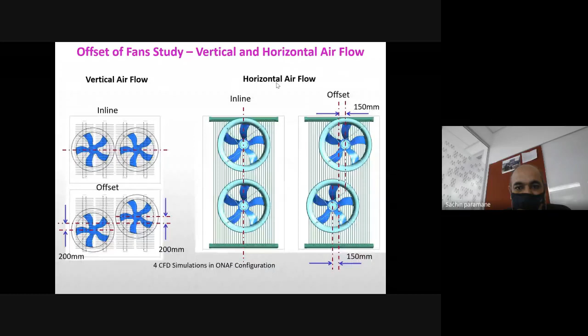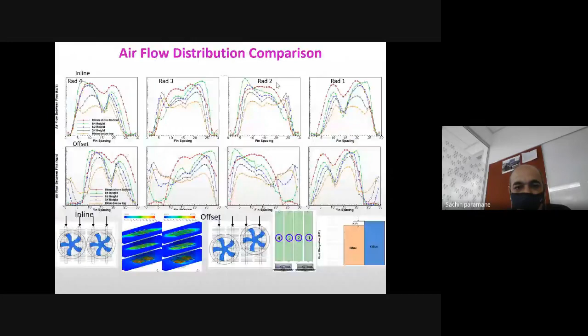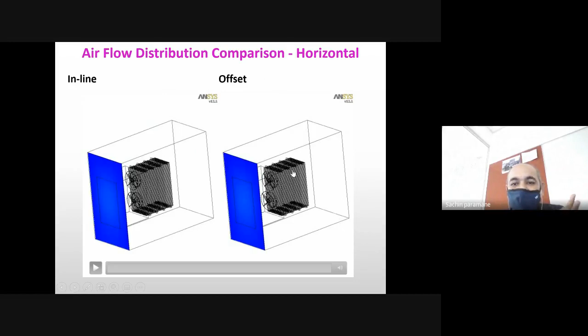fan. So this is the first radiator, this is second, third, and fourth. The radiator which is near to the fan will have the maximum amount of heat dissipation because these are getting cold ambient air. As distance from the fan increases, the air picks up the heat from these radiators and becomes hot. And then for the end radiators, actually hot air is blowing over the radiator.